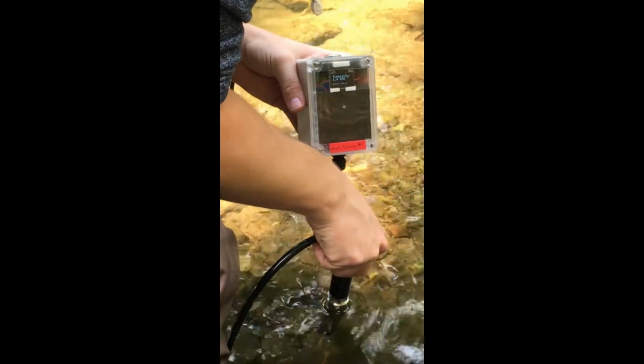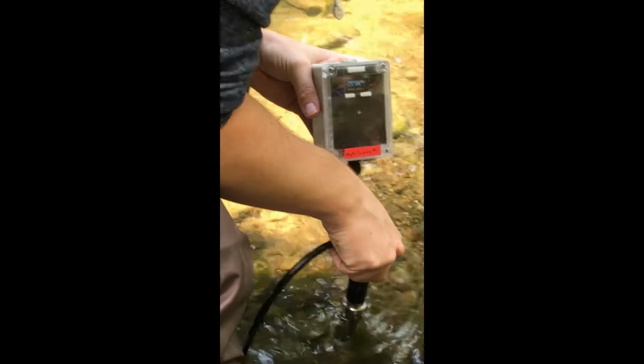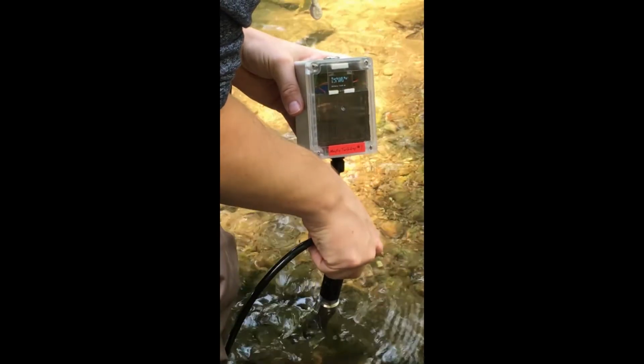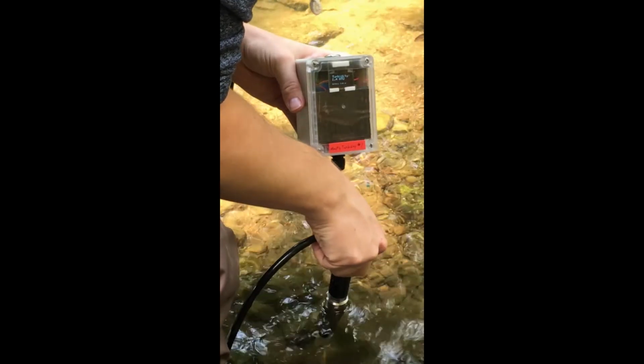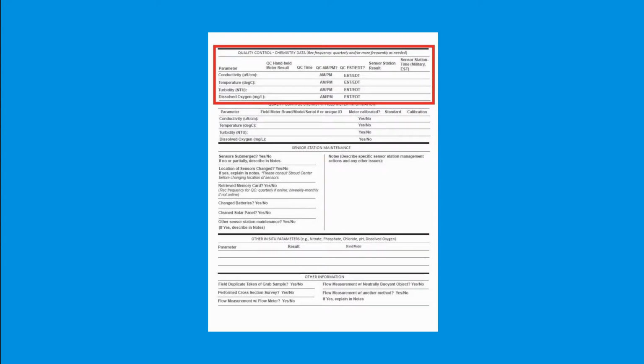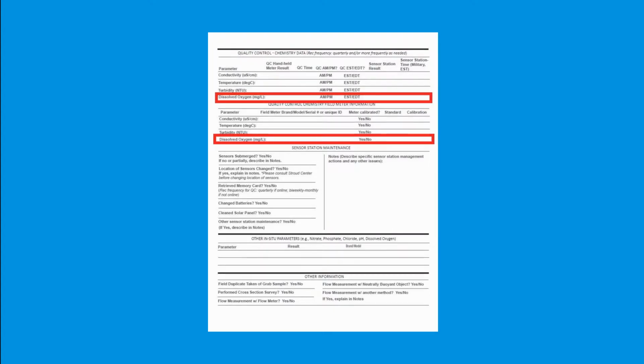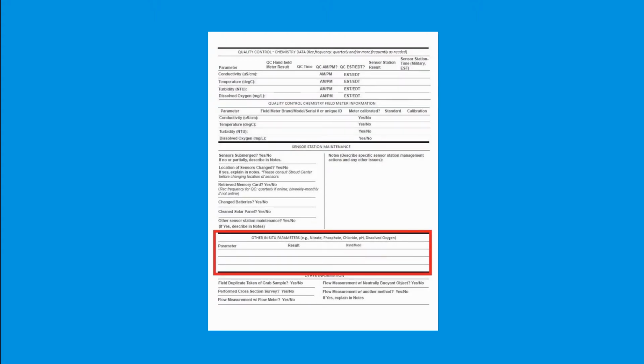After a few seconds, the screen will show the value stabilizing within a small range. Sometimes a single value will stay on the screen. Usually, the median of the range is considered the instrument's value. The measured result and time it was taken is then recorded on the turbidity parameter row of the Quality Control Chemistry Data section of the Field Visit Datasheet. There is space on the Field Visit Datasheet to QC a dissolved oxygen probe if the sensor station contains one. There is also blank space in the Other in situ parameters section to record QC values for additional parameters that your sensor station is measuring besides the ones mentioned in this video.